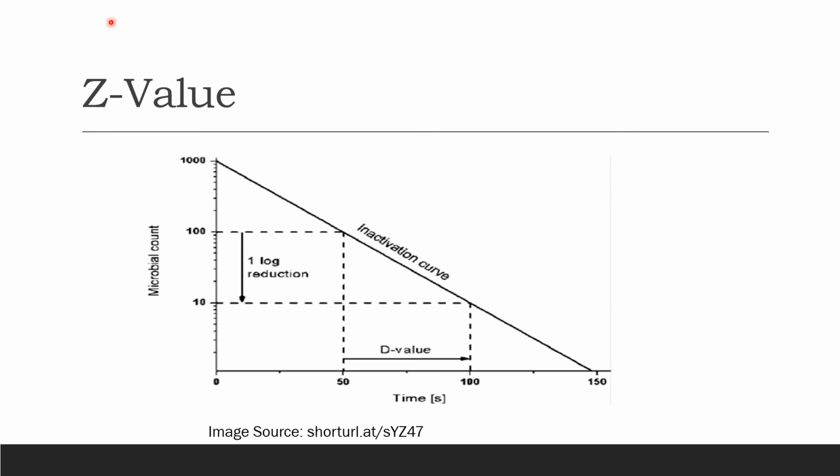The sterilization process will therefore need to produce sufficient lethality to achieve the required reduction in viable organisms. This will require exposure of the product to 8 times the D value of the reference organism. The inactivation factors associated with certain sterilization protocols and their biological indicator organisms were discussed in the previous video.